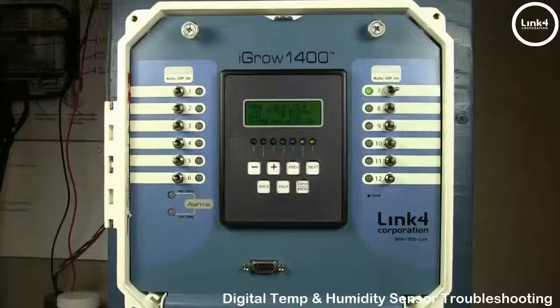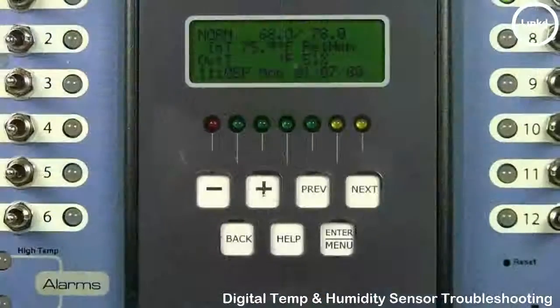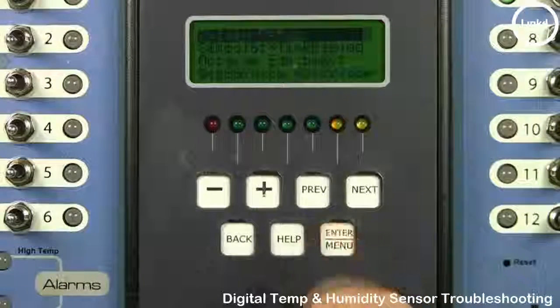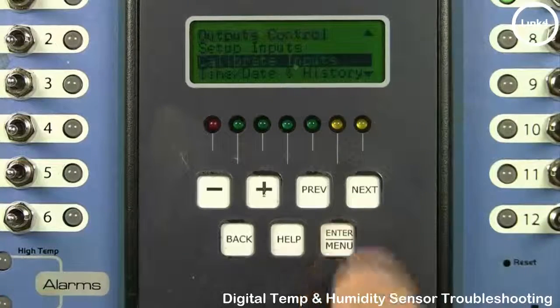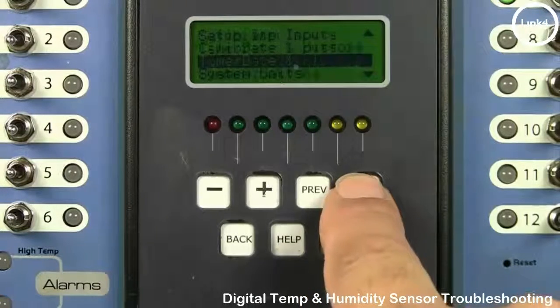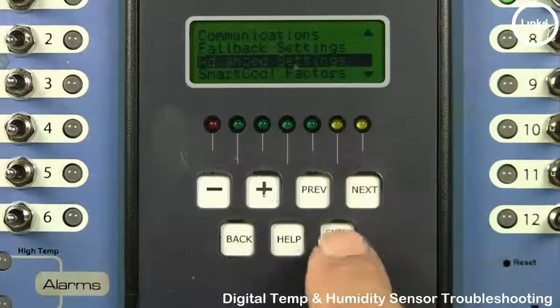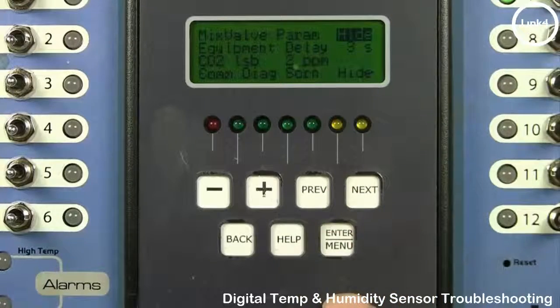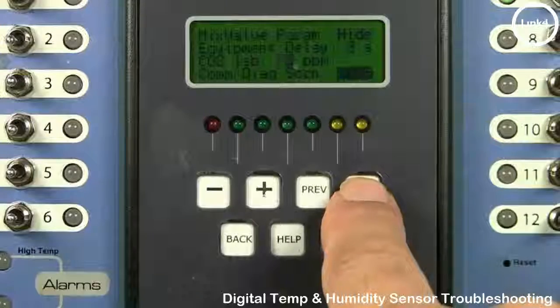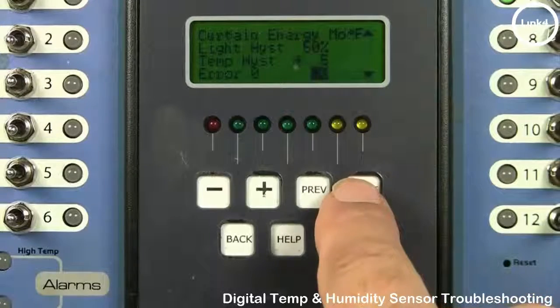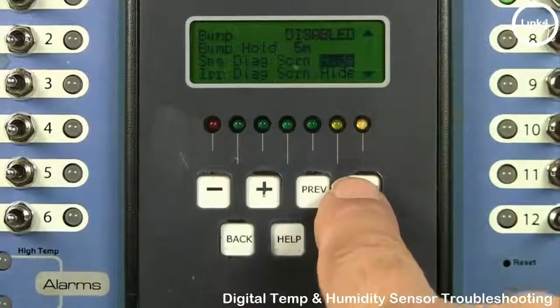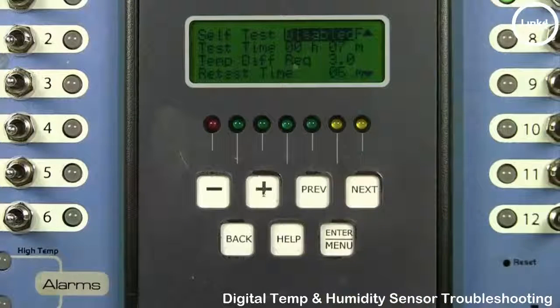First, let's examine the internal aspects of the controller's programming. Now, first we want to make sure that the sensor self-test is disabled. You would go ahead and hit Enter Menu, then go System Setup, and then scroll down in System Setup till you get to Advanced Settings. Now, in Advanced Settings, you'd hit Next until you get to the line that says Self-Test. And as you can see, the self-test on this controller is disabled.